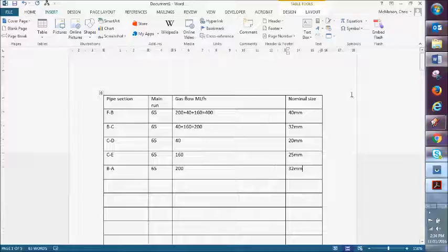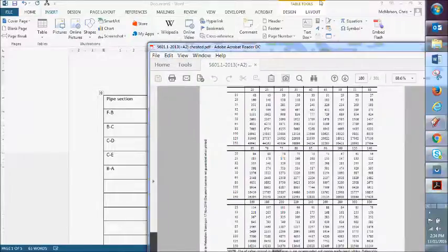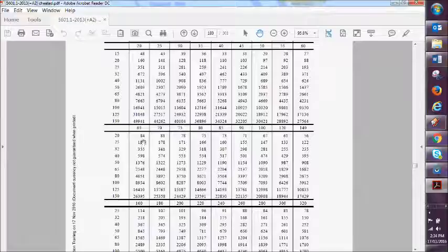You can't go down. That's why when I'm explaining it, I always say that if section A to B was 87 megajoules, you've always got to go up. You can't say, oh yeah, now 20 mil will do. You've got to go right up. It seems like overcompensation, and lots of blokes think it's a bit over the top, but it's the standards, it's the rules of the game.